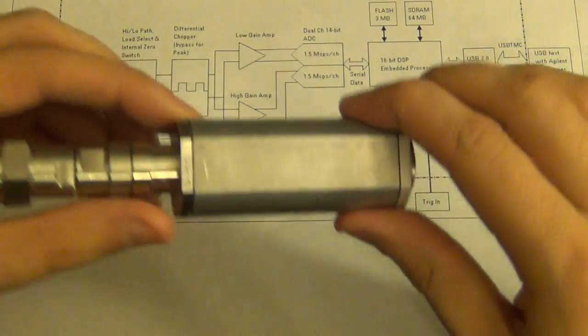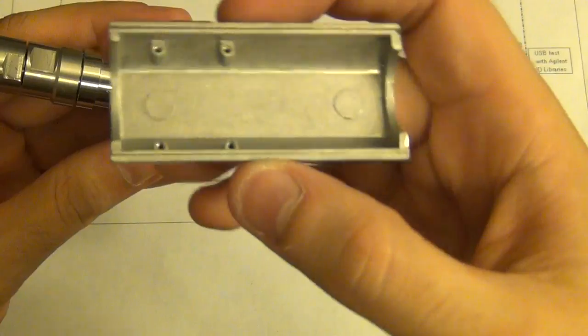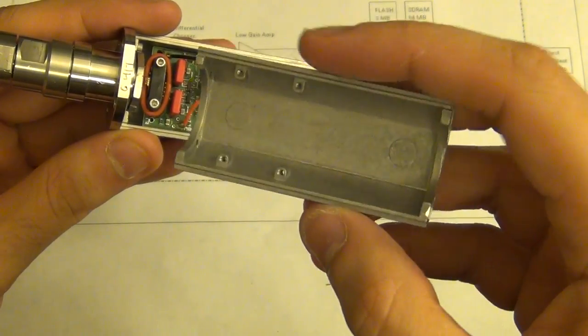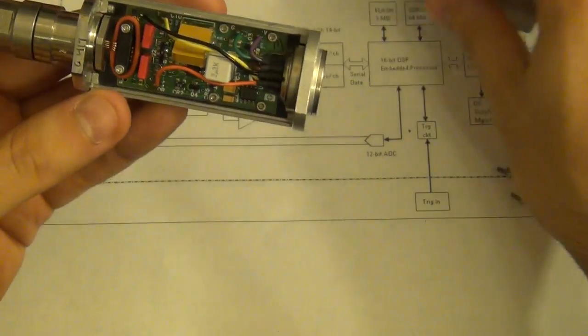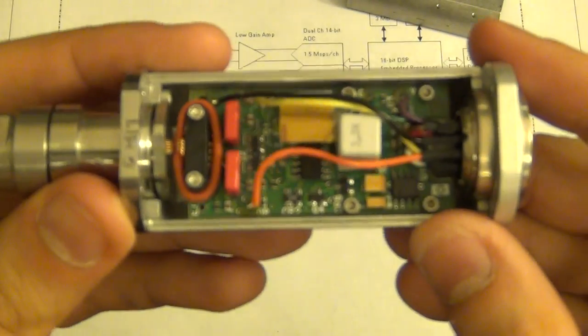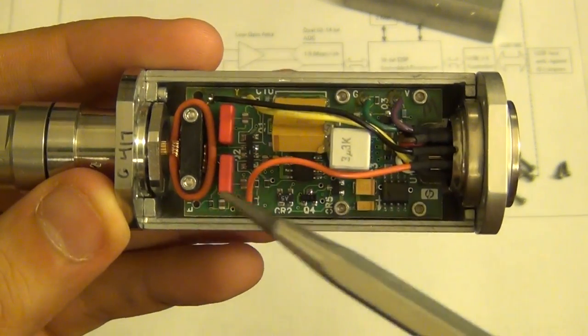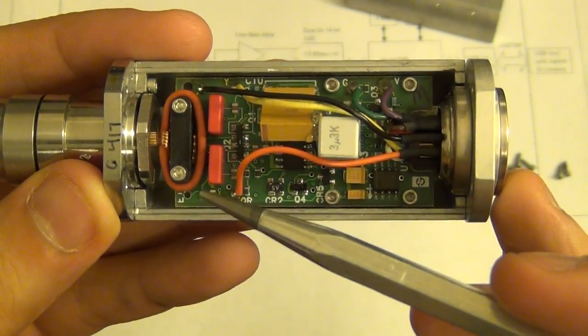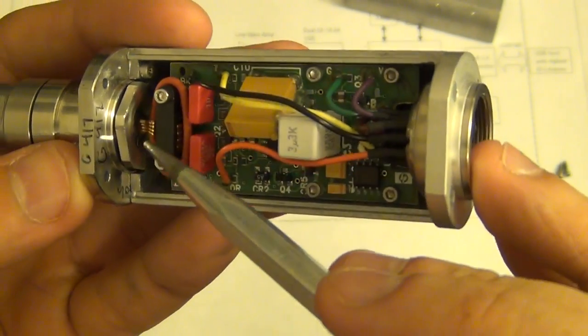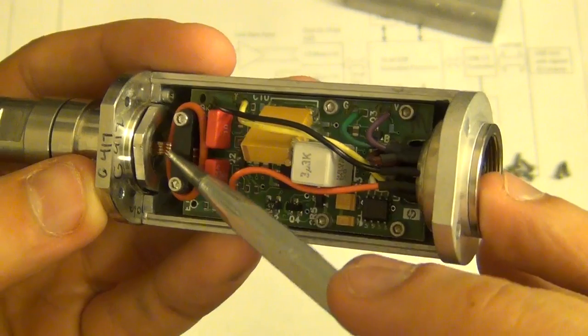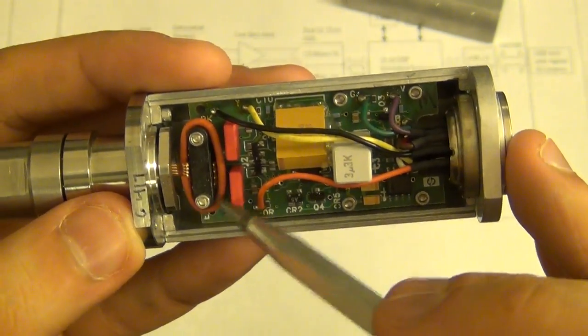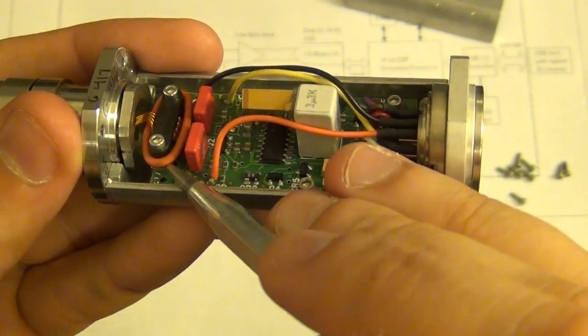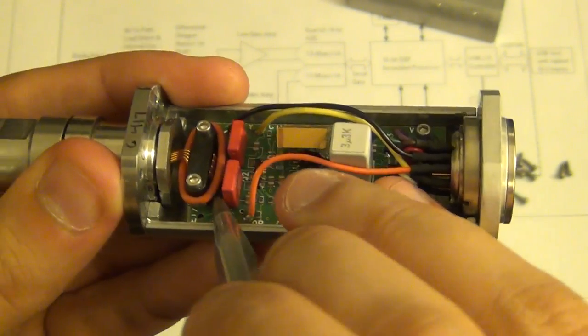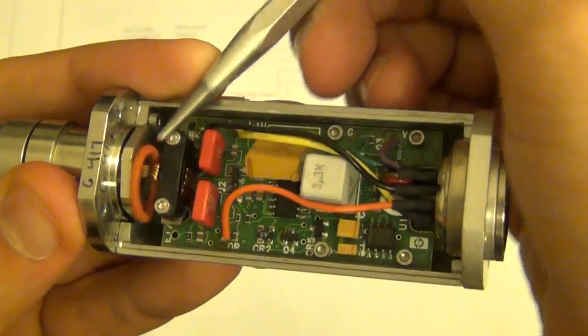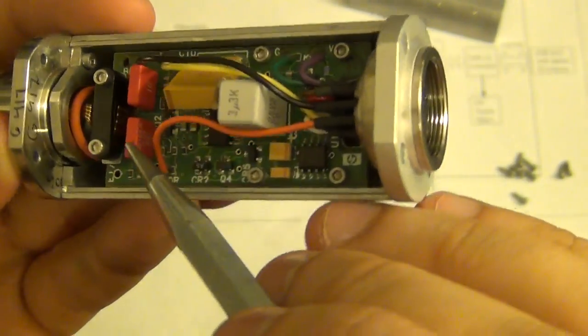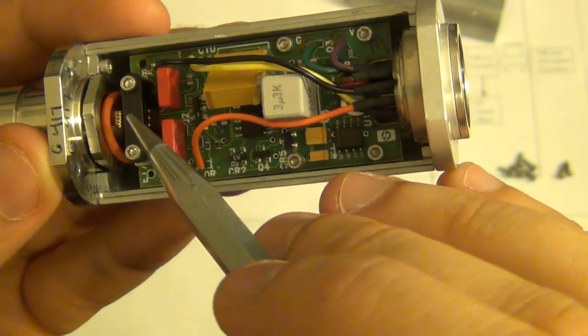Here we go. I took all the screws off, and now this panel will come out. You can see the construction of it, quite a thick piece of metal here, obviously specifically designed for this. And now you can see the internal construction a little bit better. Now that I opened this, I remember I've opened one of these before many years ago. You can see the cables coming out of the detector diodes there, and there is almost like an elastic band in here which keeps the cable in place. It's a very interesting construction. I can take this elastic piece off here, then it just slips off, and that is just so you can keep this piece, almost like a ribbon cable, in place.